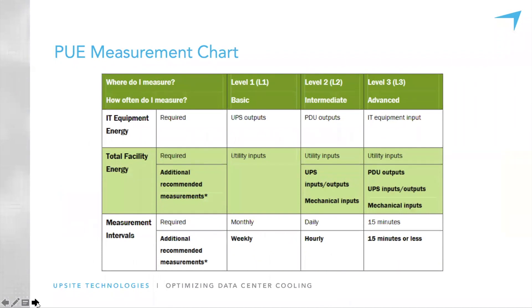This slide from the Green Grid summarizes Level 1, Level 2, and Level 3 PUE measurements — where IT equipment energy is measured from the UPS, PDUs, and rack PDU strips. It also covers measurement intervals: monthly, daily, and every 15 minutes. I was initially overwhelmed by PUE in a mixed facility — it took me 18 months to find an electric bill. But it became simple when I better understood Levels 1, 2, and 3, and I started with Level 1, measuring Monday, Wednesday, and Friday.